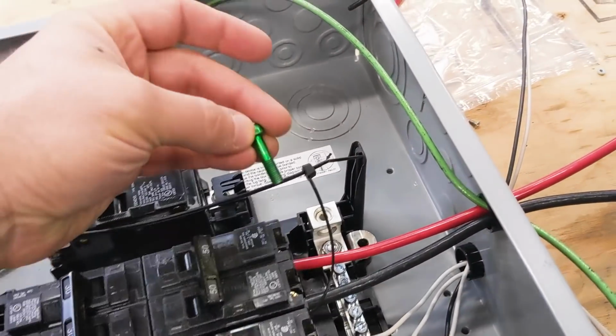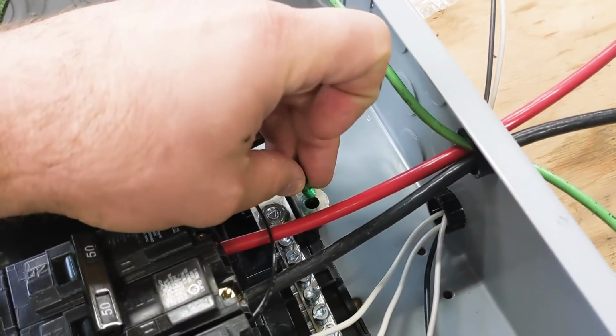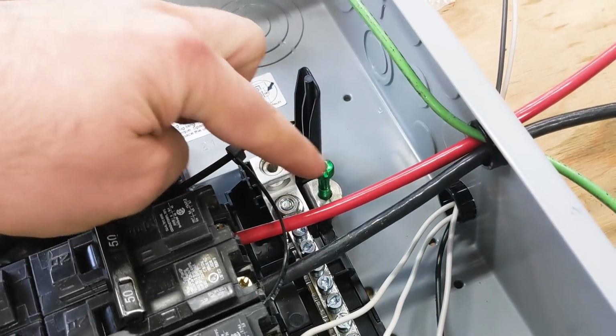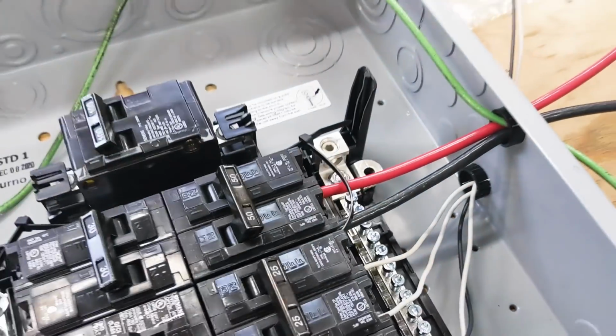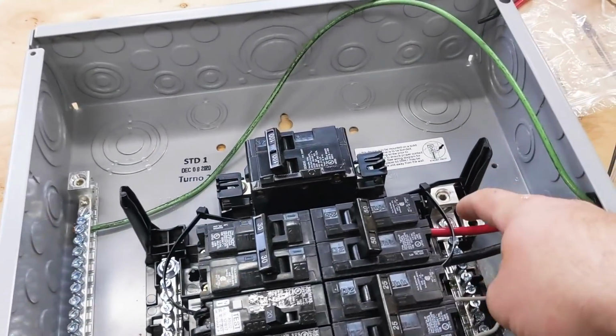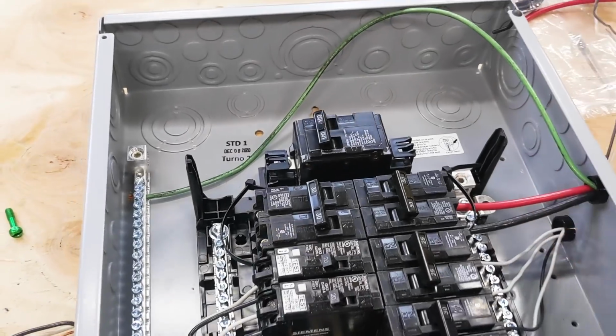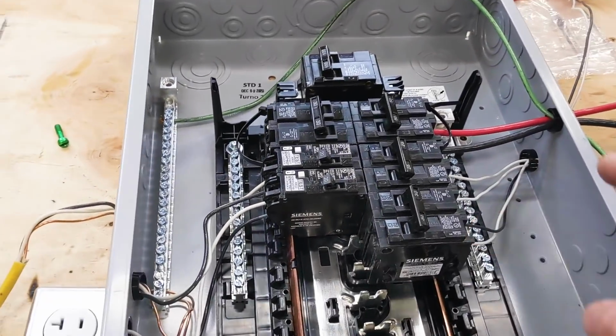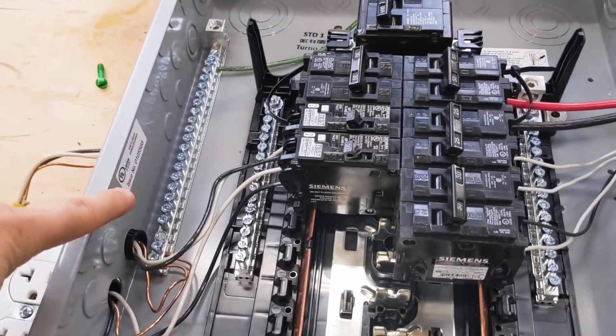I have not yet made the ground to neutral connection, which would happen right there if I tighten that screw down, because I'm not 100% sure if there's a ground to neutral connection in the inverter. I don't think so, so I need that screw, but I'll wait till I turn it on to double check that. We have the grounding bar.